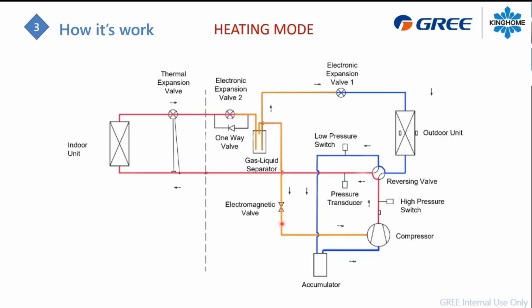The thing is, they had also an electromagnetic valve right here. This valve here is connected to the gas and liquid separator, but only from the top. So if we look here on this diagram, you will have high temperature refrigerant liquid in the base, and you will have some vapor on the top here. So when the temperature is very low outside, very cold weather temperature, well, this valve here can be active for like 1 second, 2 seconds. You will hear the clicking noise of it.